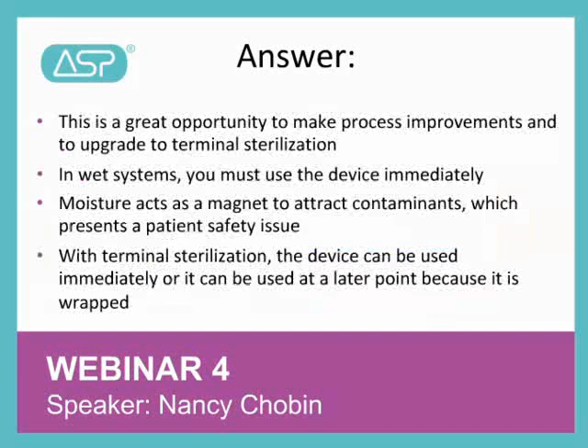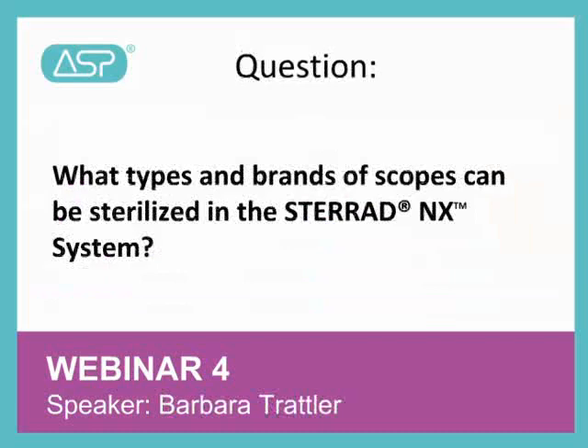Also, from an efficiency standpoint, with a device processed in a wet system, if a case is canceled or there is another reason to not use the device, you have to process the equipment again because you can't maintain its sterility. If the device is not used immediately, it must be completely reprocessed, thereby incurring additional time and processing costs. With terminal sterilization, if the device is not used immediately, you can use it at a later point because it is wrapped.